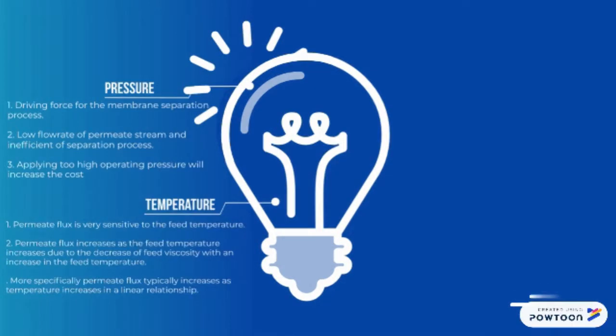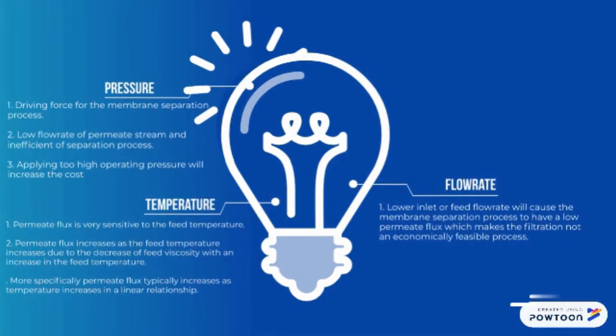Temperature can also be a factor. Permeate flux is very sensitive to feed temperature and increases as the feed temperature increases. This is mainly due to the decrease of feed viscosity with an increase in feed temperature. More specifically, permeate flux typically increases with temperature in a linear relationship. Lower inlet or feed flow rate will cause the membrane separation process to have a low permeate flux, making the filtration not an economically feasible process.